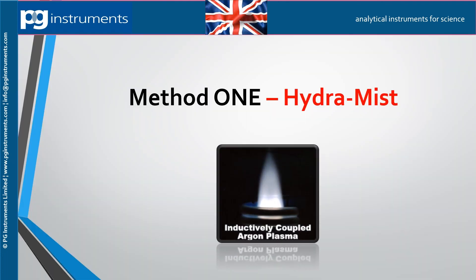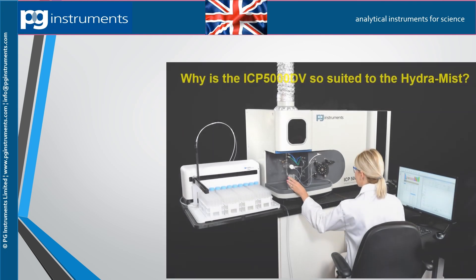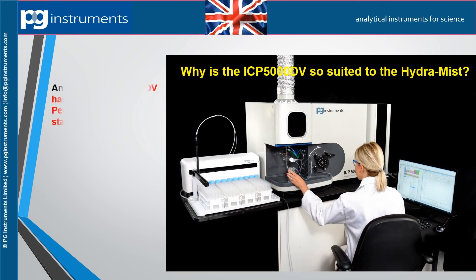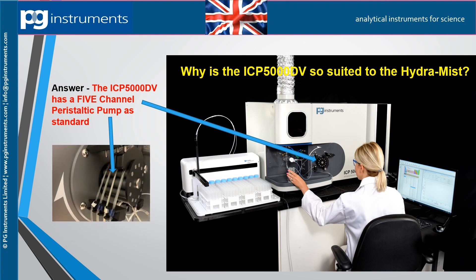The Hydra-Mist allows simultaneous analysis of hydride forming elements such as arsenic, selenium, and mercury, along with other elements such as copper, aluminium, and boron. Hydra-Mist requires a minimum of a four-channel peristaltic pump. The ICP-5000DV has a five-channel pump as standard and is perfectly suited to the Hydra-Mist.